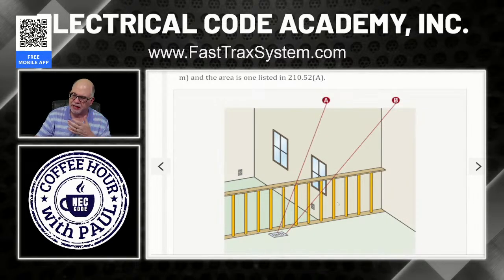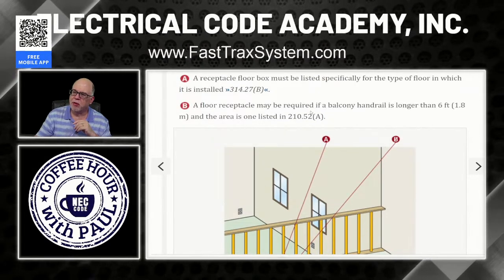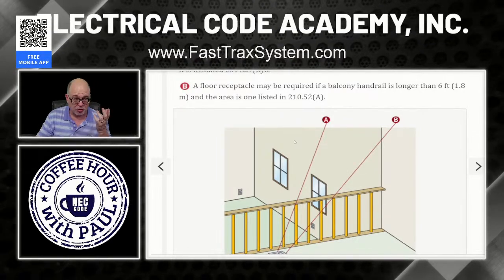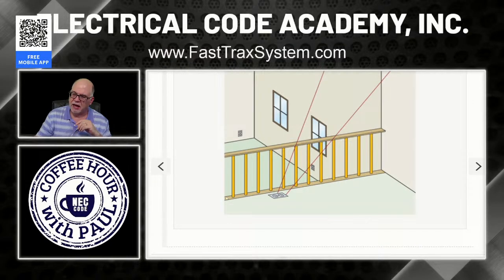Now, I obviously can't put it in here in the balusters. That would look kind of stupid. So I'm going to put it in the floor. But it has to be within what? It has to be within 18 inches of this rail. Okay. So a floor receptacle may be required if the balcony handrail is longer than 6 feet and the area is one listed in 210.52(A). So it's one of those areas that we were talking about, living room, dining room, things like that, or similar area. And in this case, if this is longer than 6 feet, all right, to the end, then obviously I have to have a receptacle within 6 feet of the end of this balcony rail, okay?